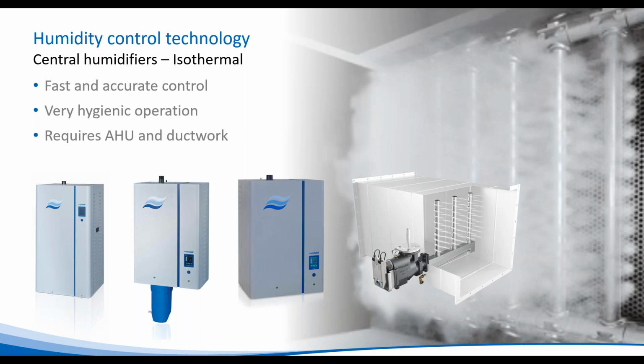So central humidifiers are used when we've got an air handling unit with an air delivery method, and inside the air handling unit we're going to have heating coils, cooling coils, filtration, and humidification. And here, typically, we're either using steam or water to increase the moisture content. And typically, it will be a humidifier like this that will be mounted next to the air handling unit or the duct, and the unit will produce atmospheric pressure steam, in this case by a cylinder that will hold water and conduct electricity through the cylinder, through the water in the cylinder to produce steam. Steam is then taken from the top of the unit through pipework to a steam lance that's inside the handling unit or duct, and we increase the moisture content by adding steam to the air at a prescribed rate.